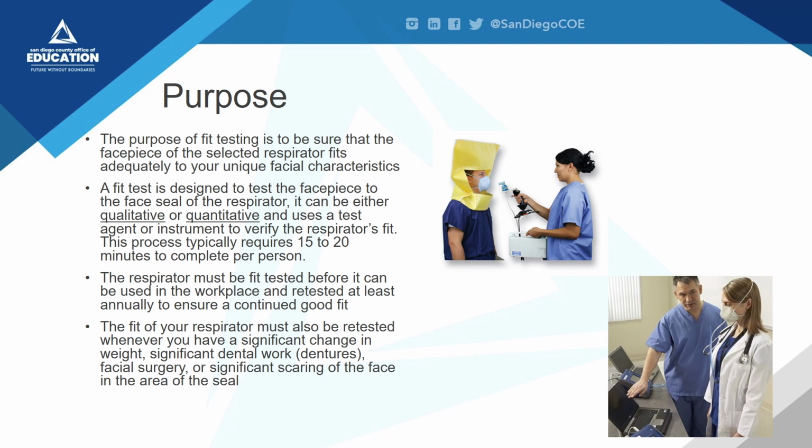Purpose. The purpose of fit testing is to be sure that the facepiece of the selected respirator fits adequately to your unique facial characteristics. A fit test is designed to test the facepiece to face seal of the respirator. It can either be qualitative or quantitative and uses a test agent or instrument to verify the respirator's fit. This process typically requires 15 to 20 minutes to complete per person.